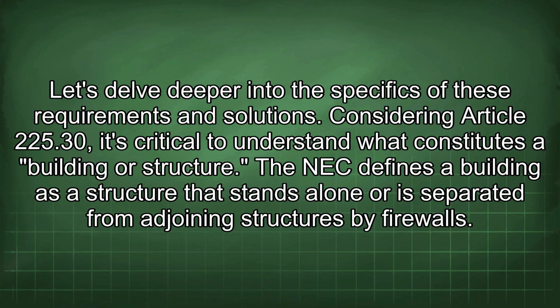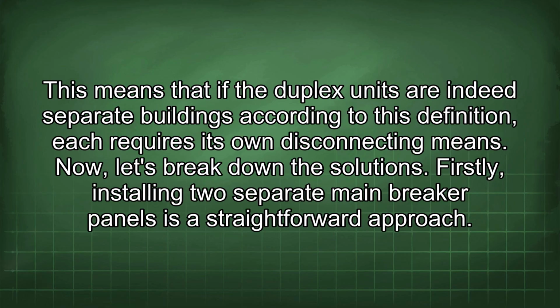Considering Article 225.30, it's critical to understand what constitutes a building or structure. The NEC defines a building as a structure that stands alone or is separated from adjoining structures by firewalls. This means that if the duplex units are indeed separate buildings according to this definition, each requires its own disconnecting means. Now let's break down the solutions.